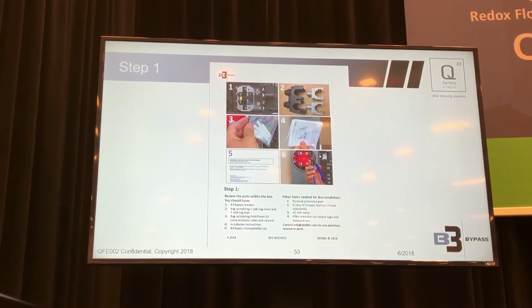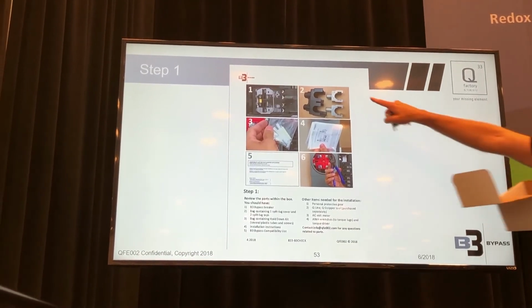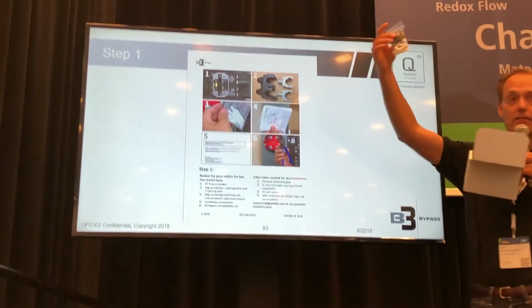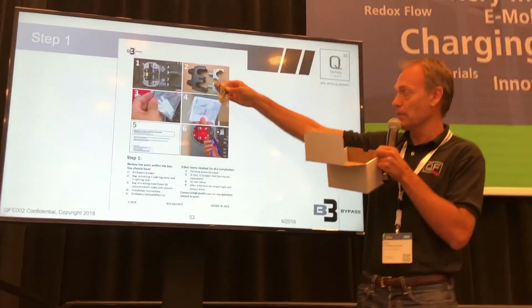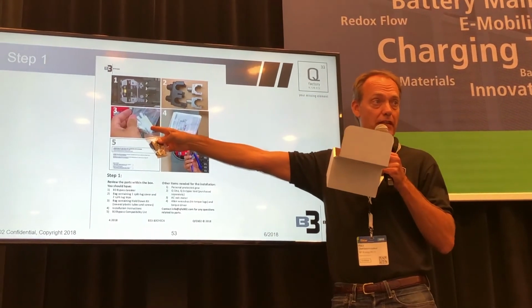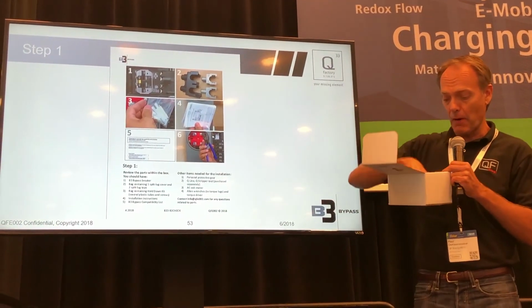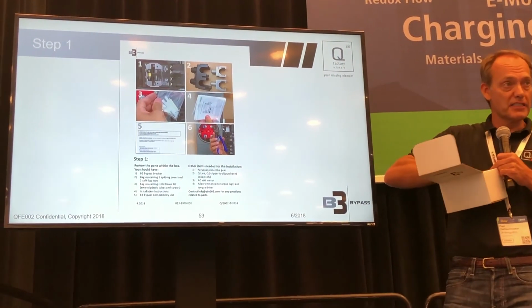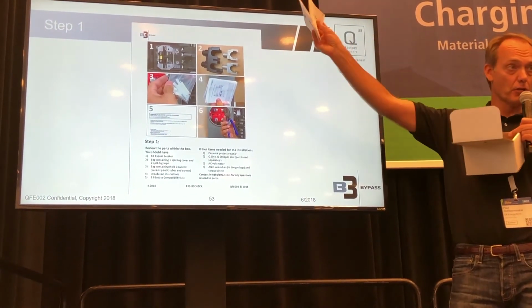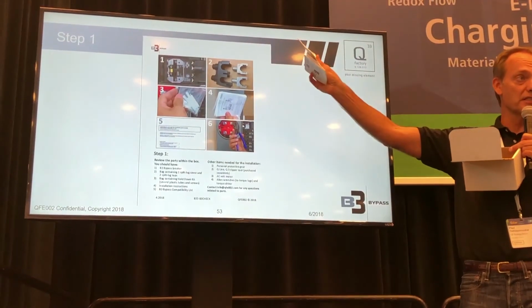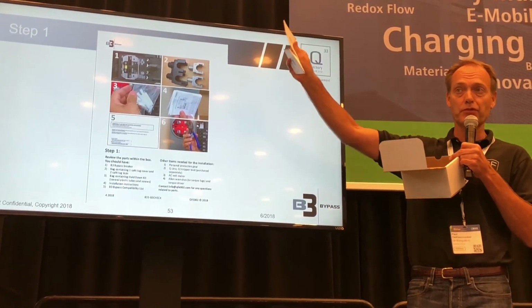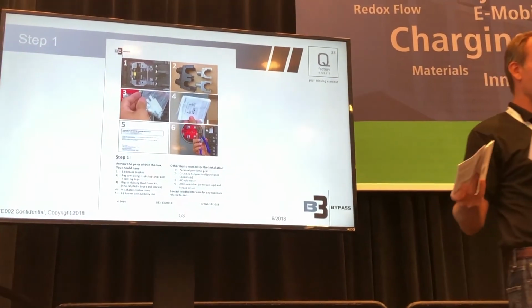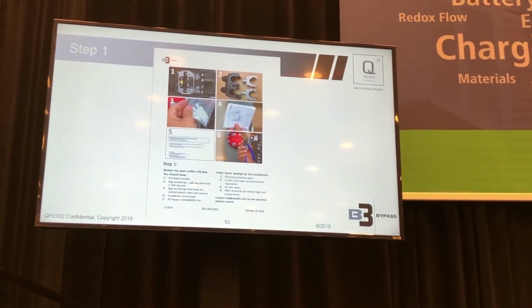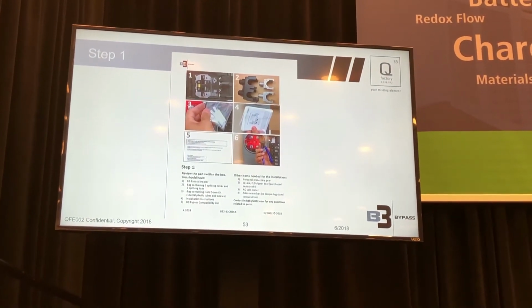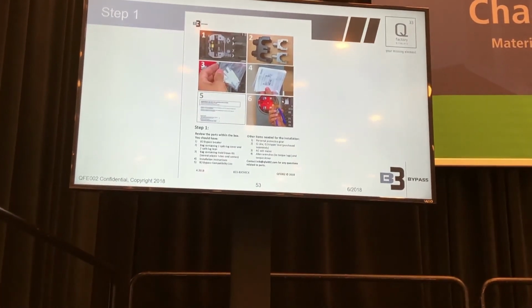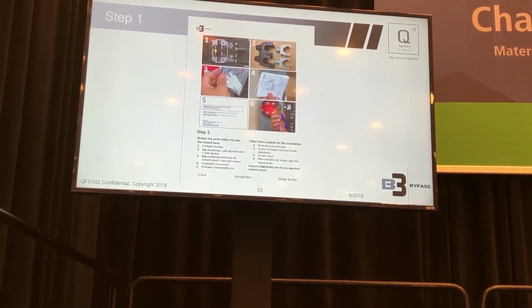All right, the breaker's included in the box. Also in the box are the split lug covers and an insulated cover for the split lugs. We also include a standoff kit that I'll explain. And then in every box, to make sure that inspectors, if they have any questions, we include paper copies of the compatibility list and the UL approved installation guide. We know you don't like extra paper at the job site, but it's a new product, and we want to make sure if the inspector says, where's the installation guide, where's the compatibility list, the hard copy's right here, okay?